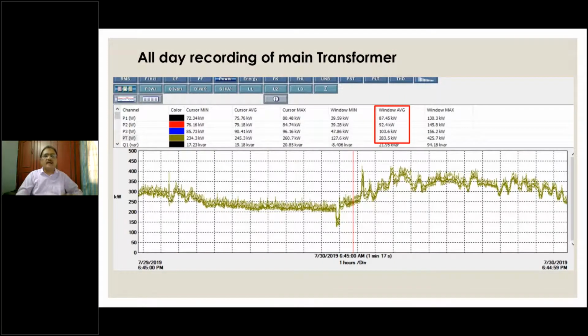This is the 24-hour data of kilowatt. You can see here that on 29/7/2019, 6:45 p.m., the recording started and ended at the same time on the next day. So this is a 24-hour window, capturing data of active power in kilowatt. The cursor is where I keep it. The cursor has minimum, average, and maximum, and the entire 24-hour window has minimum, average, and maximum. We'll take the average and ignore the minimum and maximum. So the average load for that particular day in the hospital was 283.5 kilowatt.